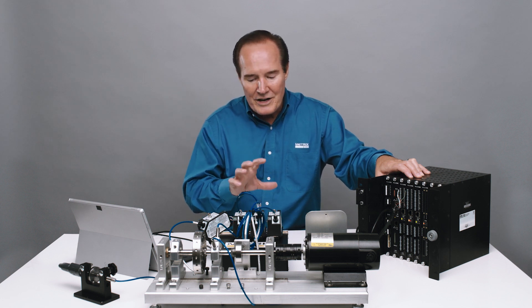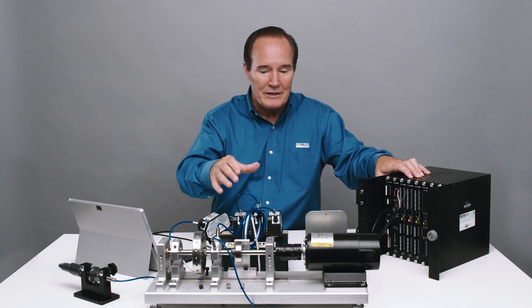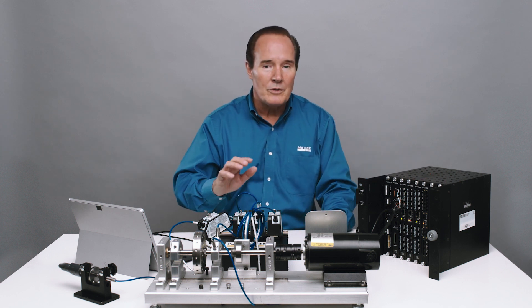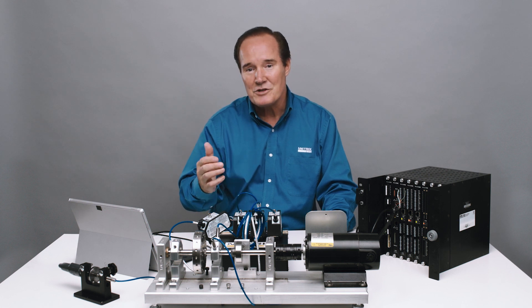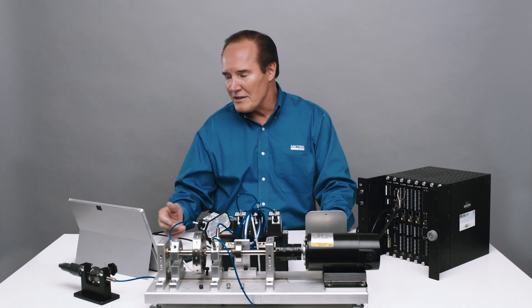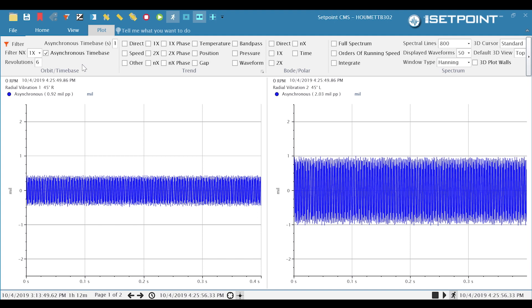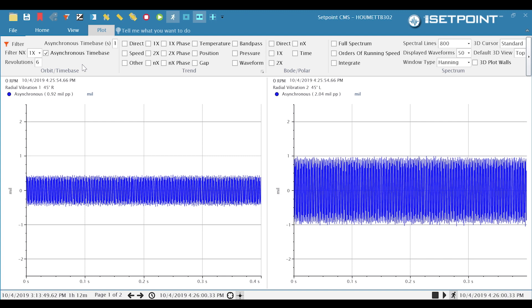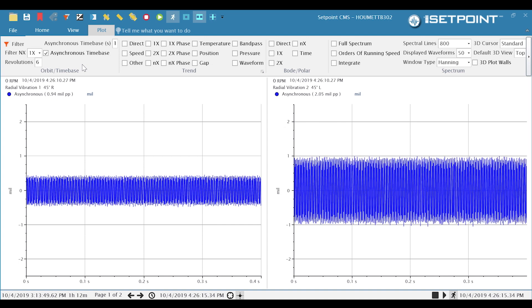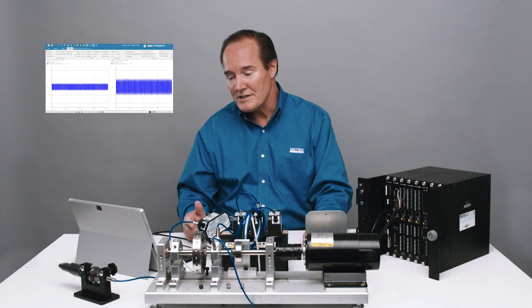Our transducers are energized but the rotor is not running. What we're going to look at is the software to see this noise problem. When I look at the set point software, we're getting data live right now. You can see on the Y transducer, which is vibration channel one, we have 0.92 mils peak to peak of vibration. And then on channel two, we have 2.04 mils peak to peak — and the rotor is not even running. You can tell right away by looking at that signal that it's a noisy signal.